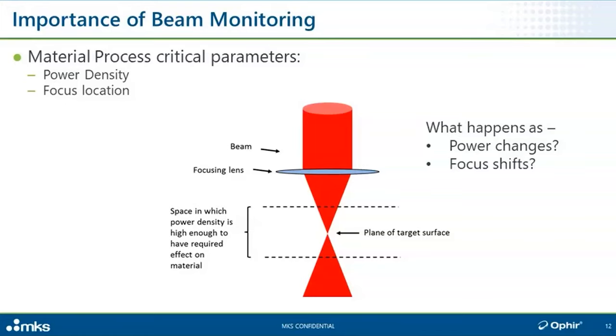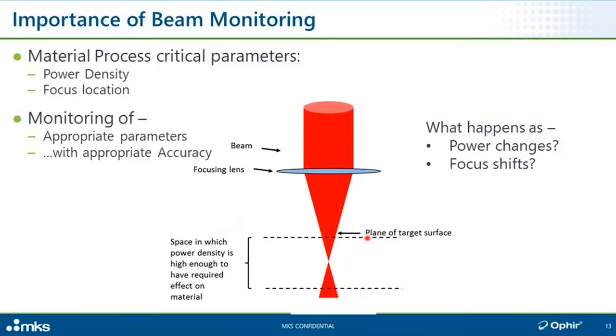So here we see the space within which we have the required power density, and somewhere smack in the middle of it is where we're going to put our target workpiece. We design and program the system so that the user punches in a given application and the system sets up the exact electrical parameters, the appropriate drive current and whatever it may be, such that a beam with the exact optical parameters will be generated. But what happens if the power drifts due perhaps to aging of some components or say heating effects, changing the optical characteristics of the focusing lens, and therefore the focus ends up shifting? We can suddenly find ourselves with the target workpiece outside the space within which the power density is high enough to do the work. So we may end up with the process not working or working, but not well.